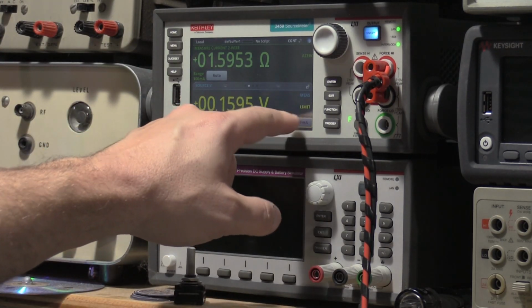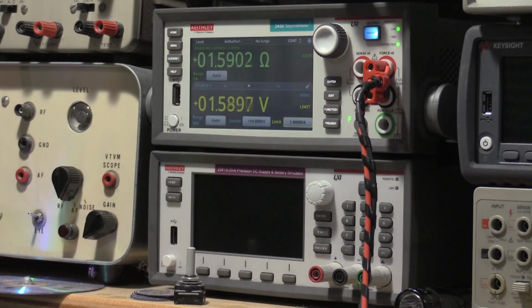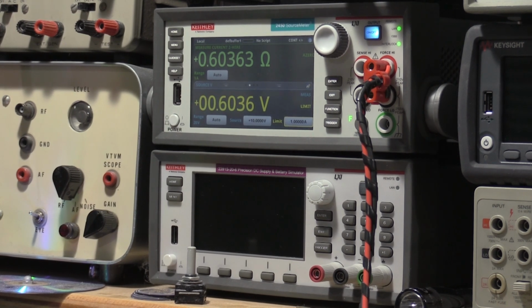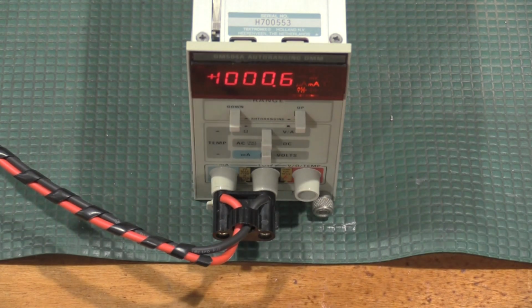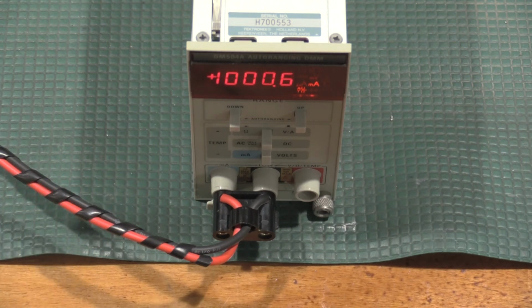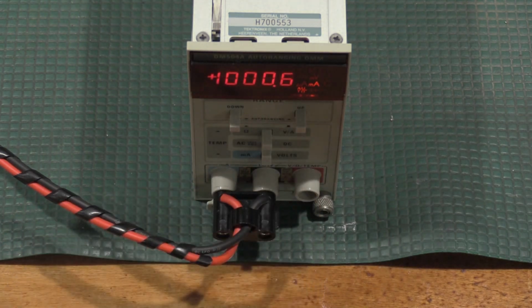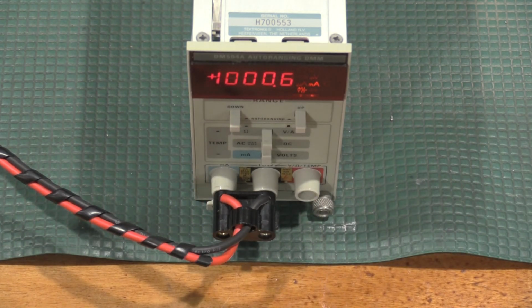Okay, let's punch it a little bit, and we will give it an amp. Oh, isn't that fun? At an amp, I did hear a relay click, so it probably changed the current sense resistor in the unit, which is why we have a different resistance reading. This one's 0.6 ohms versus 0.15. But we have 1000 milliamps of current. Everything is looking good. If I remember correctly, this thing tops out at 2 amps. Oh no, 1 amp. So 1.05 is as high as it's allowed to go. So I'm pushing the SMU about as far as it can, and everything really looks good.